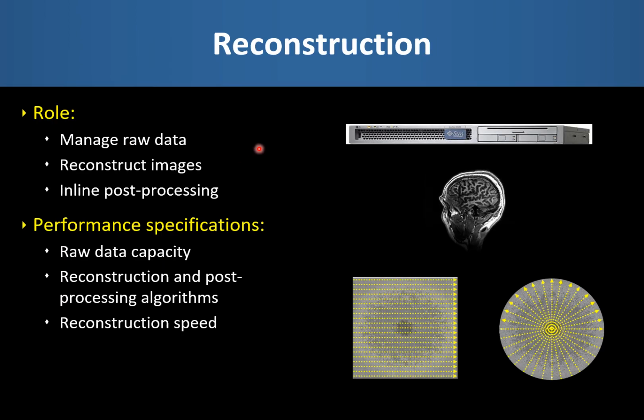The final component of the MRI system hardware is the reconstruction engine, and its role is to manage the raw data, particularly as higher resolution multi-coil data may generate very large volumes of raw data. The reconstruction software will be optimized to run multi-dimensional fast Fourier transforms, as is needed for this multi-coil 3D acquisition of over 200 slices. The recon system will also have to perform the multi-channel image combination as well as any other additional image processing that is required. And in today's world, most of the MRI system vendors are now incorporating deep learning algorithms into their reconstruction pipelines.